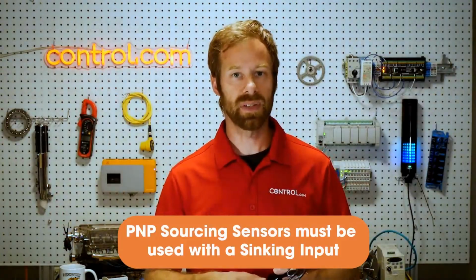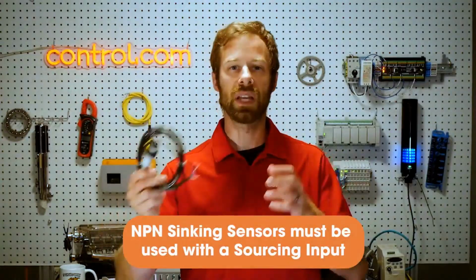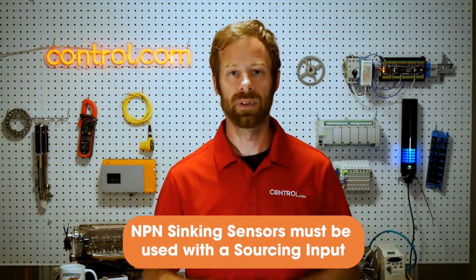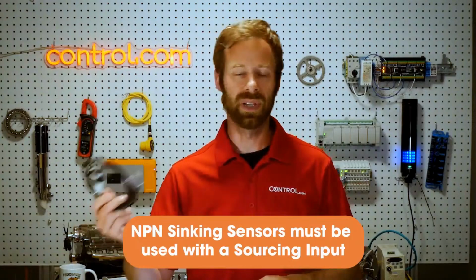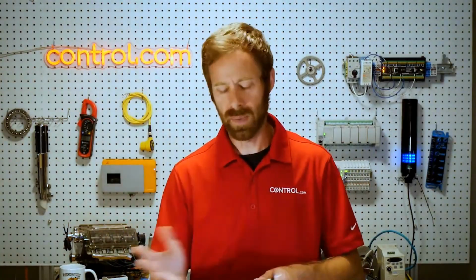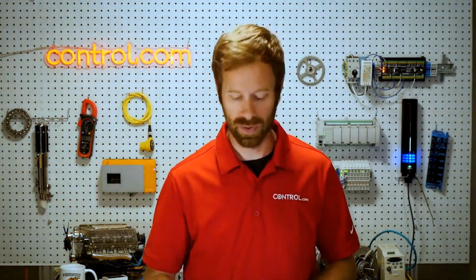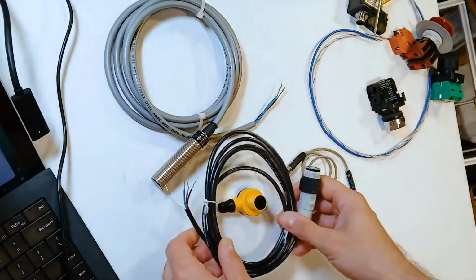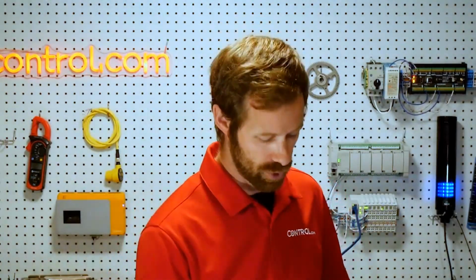They must be opposites. So if we have an NPN sinking sensor, on the other hand, we have to use a sourcing input module. So it's often the input module that dictates what kind of sensors we need, although that depends on which came first, the sensors or the control system. But the sensors are a lot cheaper, so often they are going to be chosen based on what the PLC itself needs. So these are a couple of the most basic forms of sensors to provide digital or discrete inputs, that on-off signal that goes between the field and the control system.